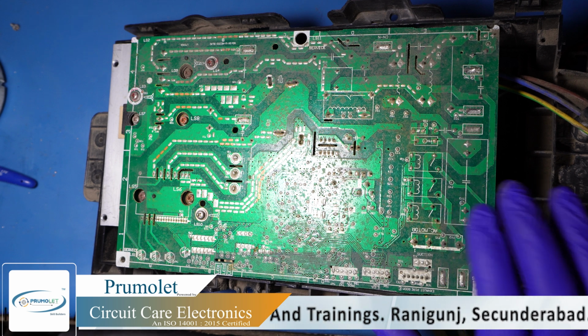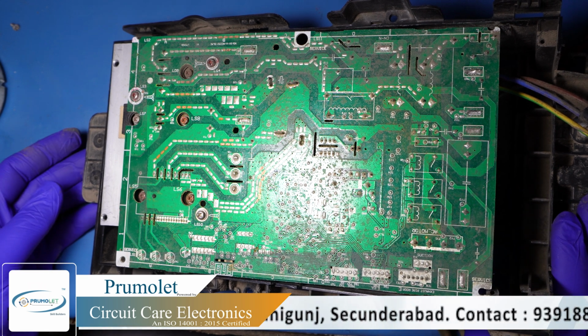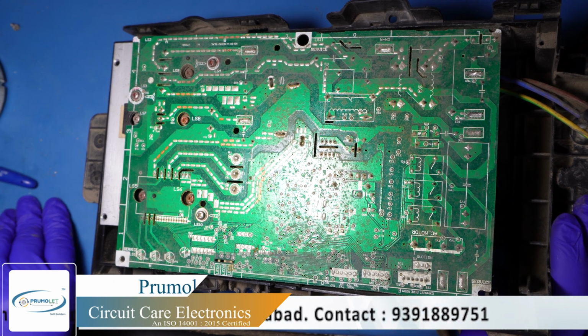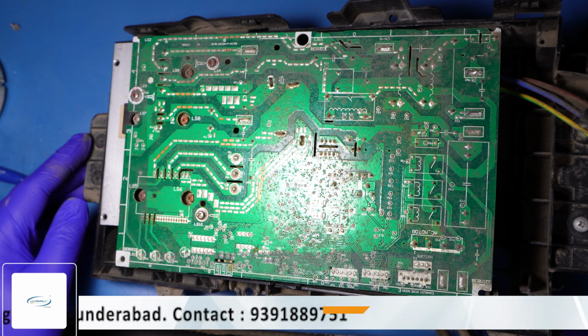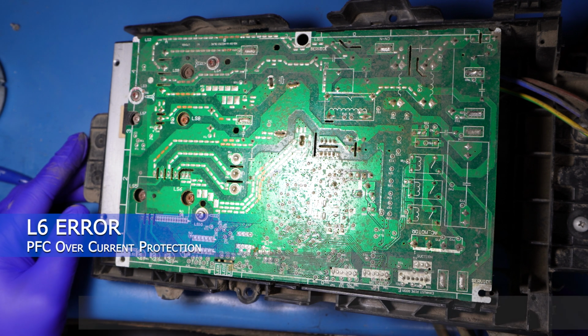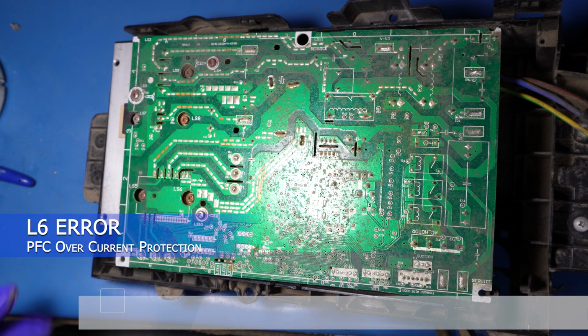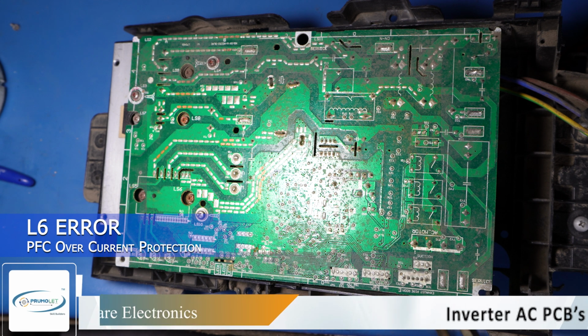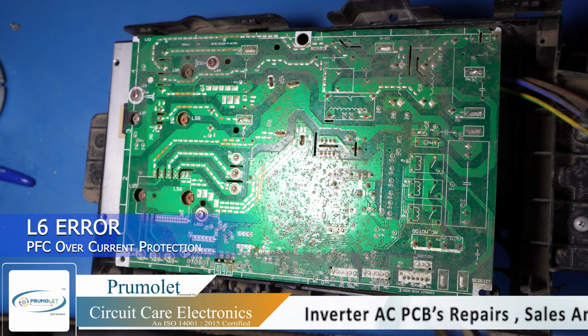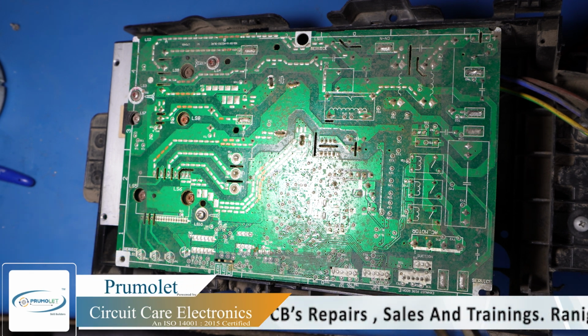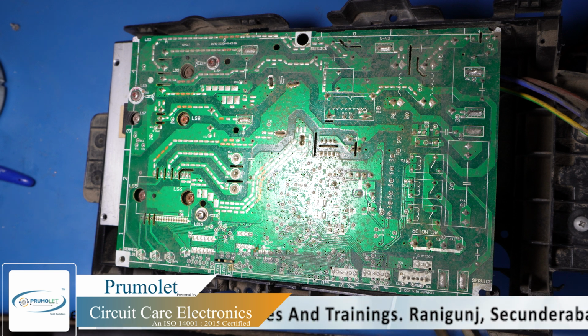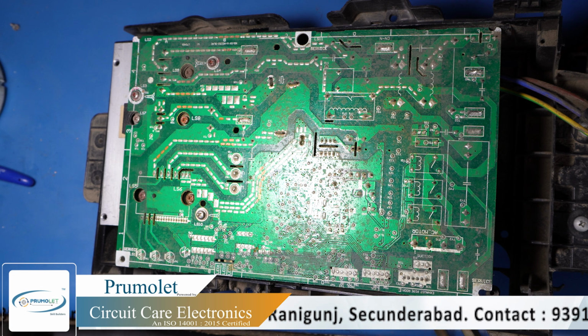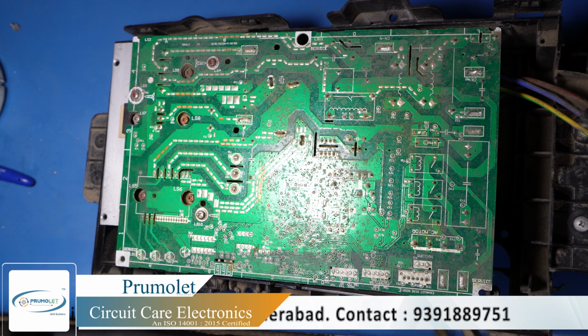This PCB is a reconnect. The error given by the customer is L6. The reason for L6 is PFC overcurrent protection. If you see the error code data of this PCB, this is it.